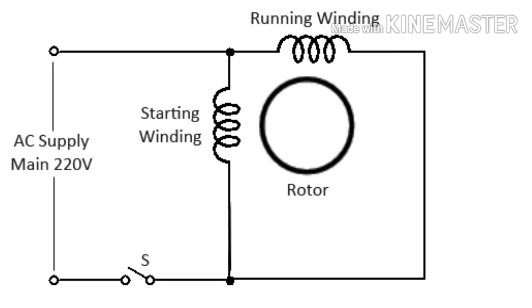Let us imagine a scenario in which the capacitor is not used. The same phase — 230 volts or 110 volts — will enter into both windings: the running winding and the starting winding. Because of this same phase entering both windings, no magnetic rotation will be created, and as a result, the rotor will not rotate and the fan will not start.